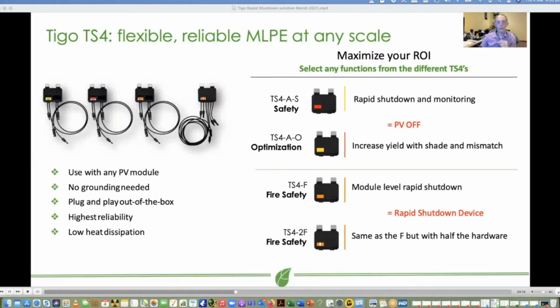And the other great thing with the monitoring is, I had a client just brought to my mind, a commercial client that put some modules on their roof. It was a 1.4 megawatt install, as I recall, and they didn't want to use tilt frames because of the cost, so they elected to lay flat. In a very short space of time, they realised they were losing 10+% production through dust. So they then had to engage a cleaning process, somebody to get on the roof and clean it. That was an additional cost, and it was quite a high cost actually. Had they had monitoring attached, they would have had a clear indication of their power loss over time, and they could make a more informed decision about when to have their modules cleaned. It might have meant that the gap between cleaning would have got a little bit longer. But as it was, they were doing it, I think, monthly. So that was quite an impost for them.